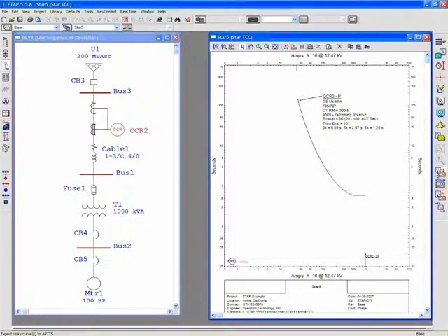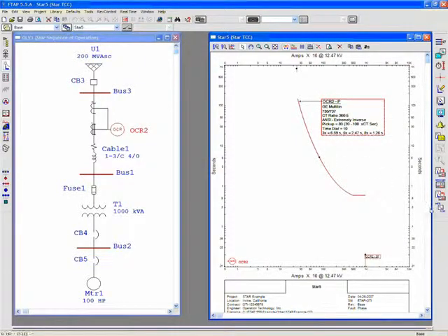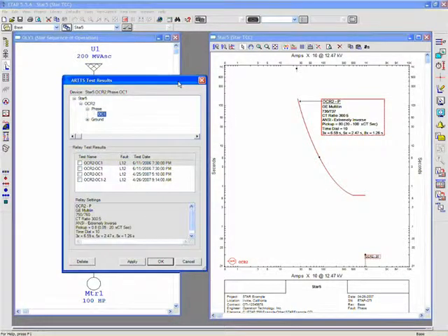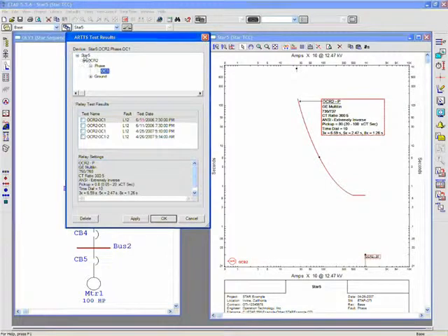And there are some tools on the bottom of the screen that indicate export curve, relay ARTTS test set, import results, and then compare. So before we actually export this data into ARTTS, we want to see what we have for this relay. So I first select the curve, and I click on the ARTTS result comparison, and this will pop up a dialog box which indicates my device curve or STAR TCC called STAR file, and here I see my OCR2 relay, and within that I see the two categories, phase and ground. Since we're dealing with the phase, we're looking at phase OC1.